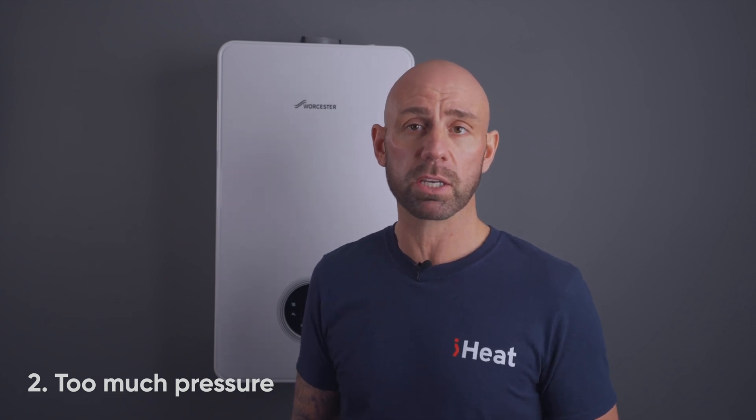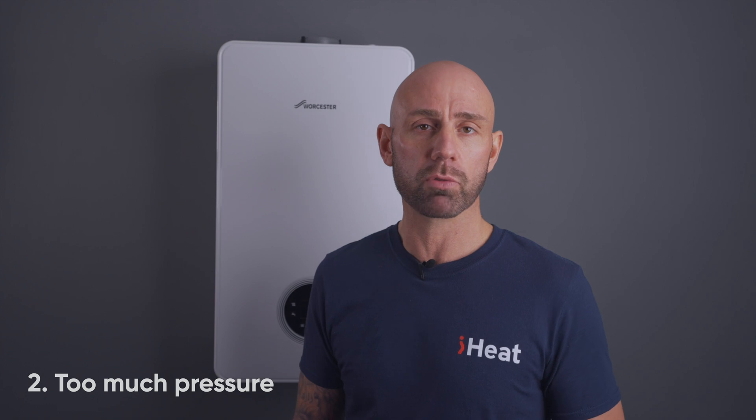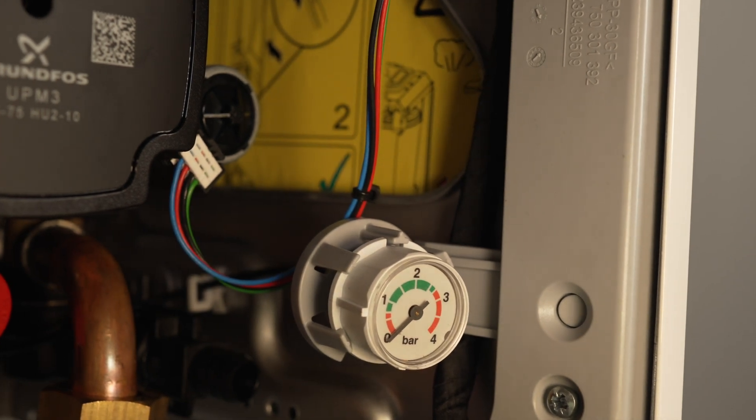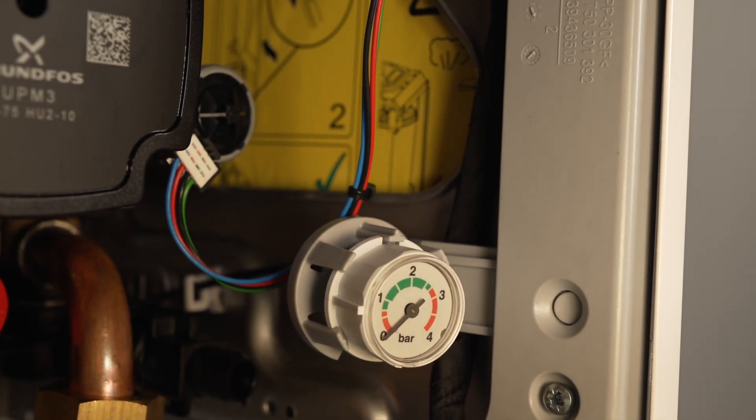Fortunately, most boilers have a pressure gauge on the front of the device. It usually has a green marking that displays the right levels of pressure for your boiler. On some of the newer Worcester Bosch and Viessmann boilers, these are now built directly into the digital screen on the front — they also have a backup mechanical gauge, which you can access by taking off the front of the boiler. If the pressure on your gauge is too low, we have a separate video on how to top up your boiler's pressure. You will need to address the leak on the system before topping up the pressure, as this could make things worse.